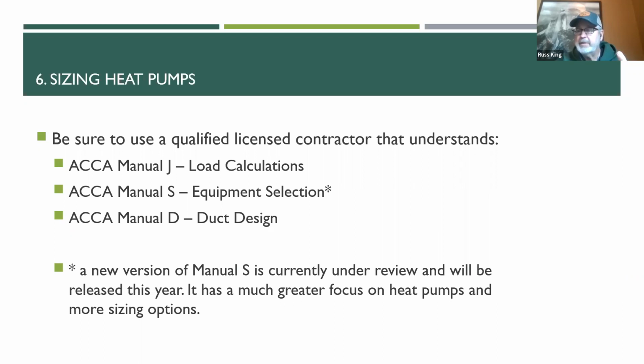Manual J does the load calculation. That's figuring out how much BTUs are entering or leaving the house. Manual S tells you how to pick a piece of equipment that will match that load. And then Manual D is how to design ducts to have good airflow and good air balance throughout the house. Okay. Just so you know, Manual S is being revised as we speak. I'm helping out with that actually. But by the end of the year, a new Manual S will be out, and it spends a lot more pages on heat pumps. Okay. It has a lot more alternative heat pump sizing opportunities in the new Manual S.